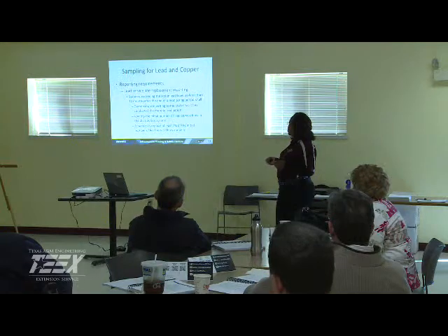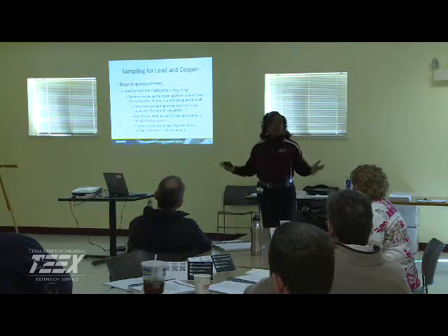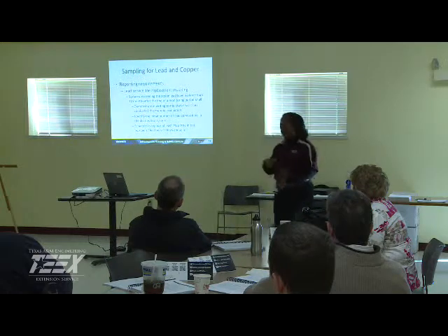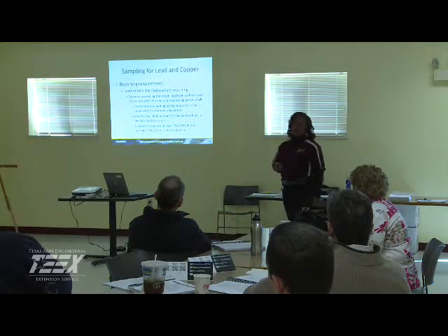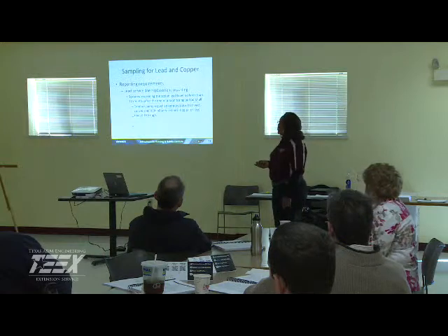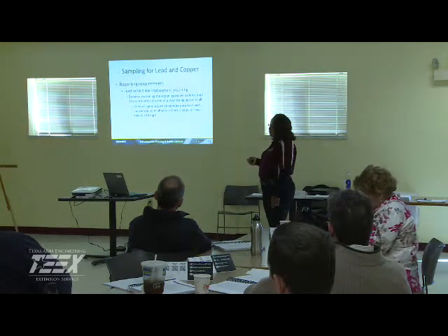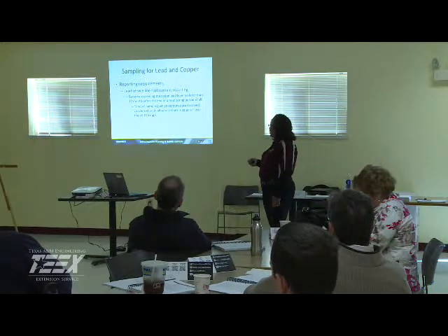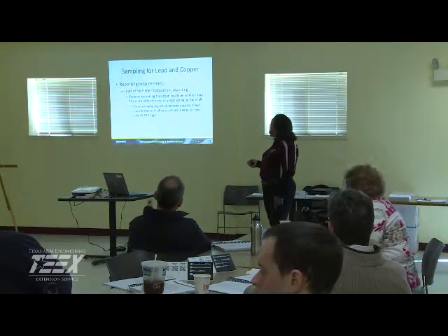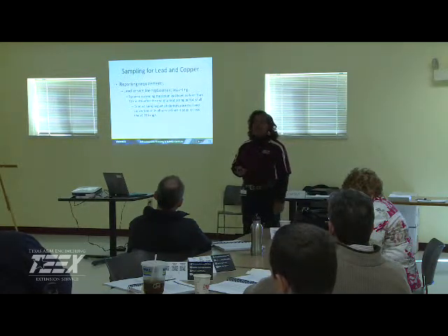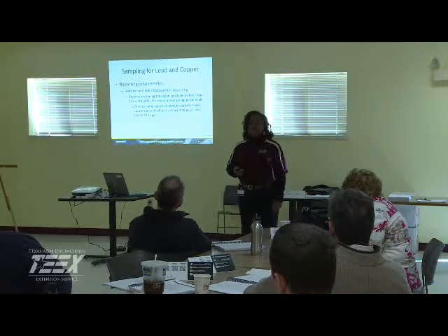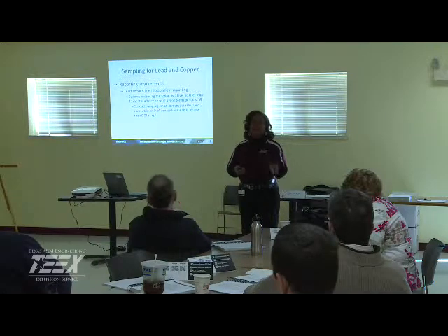Identify the initial number of lead service lines. Once you identify, get to work. Start replacement of those. You should schedule to replace at least 7% of the initial number of lead service lines on an annual basis. In addition, conduct sampling that demonstrates that lead concentration in all your service lines is equal to or less than 0.015, which is what? The MCL or the MCLG? MCL, very good. What was the goal for lead? 0.